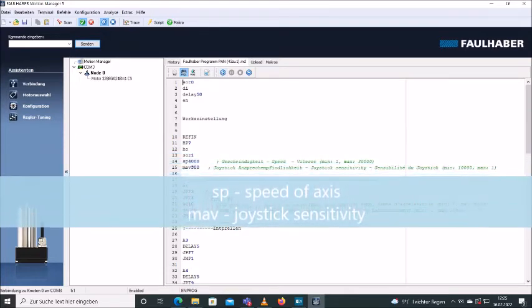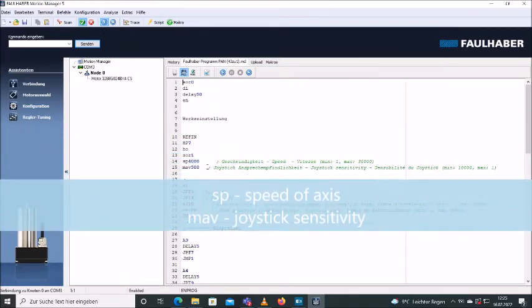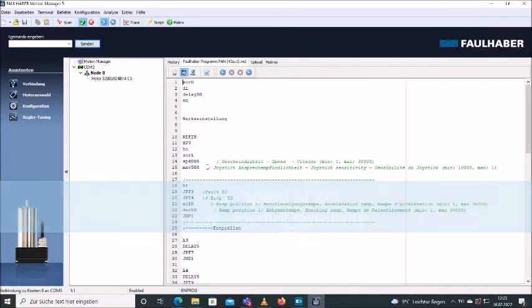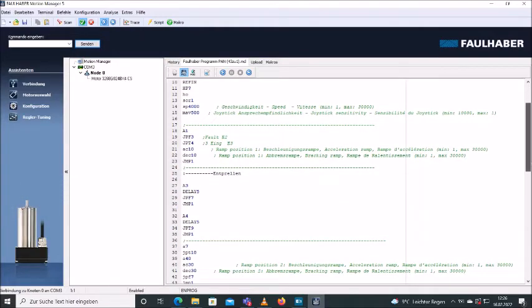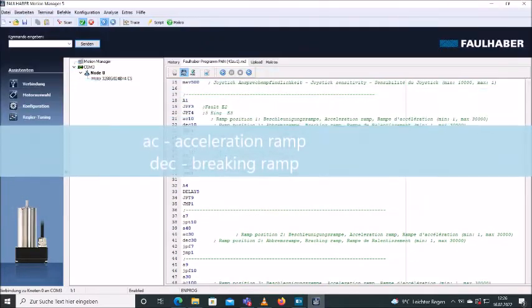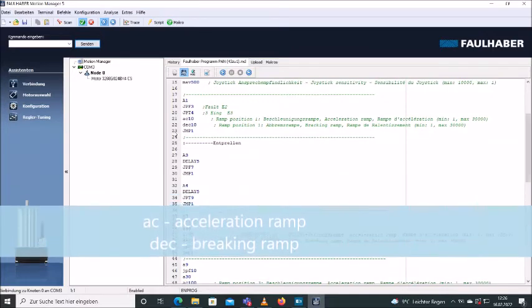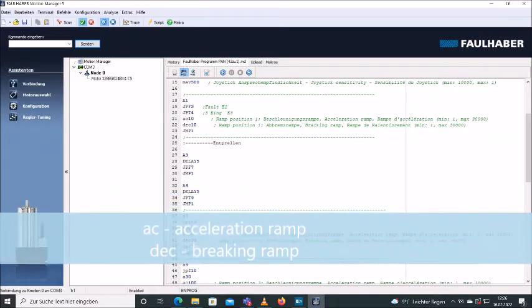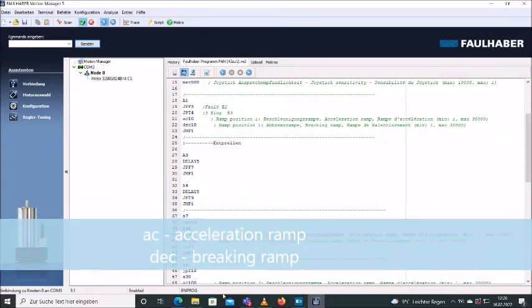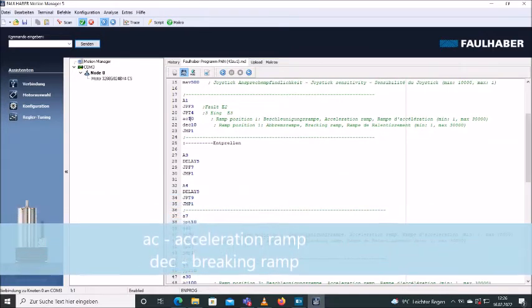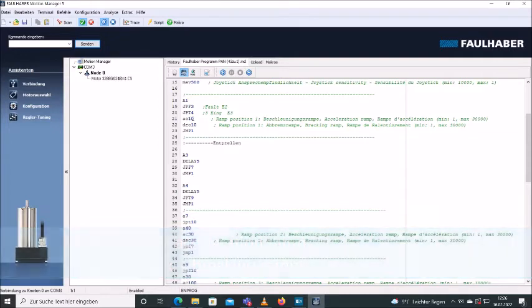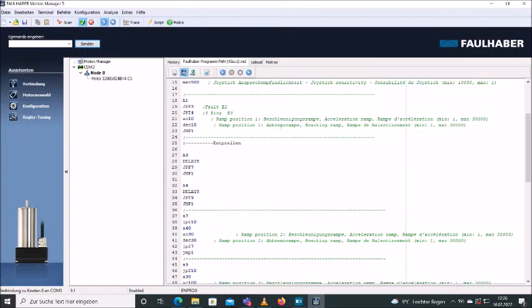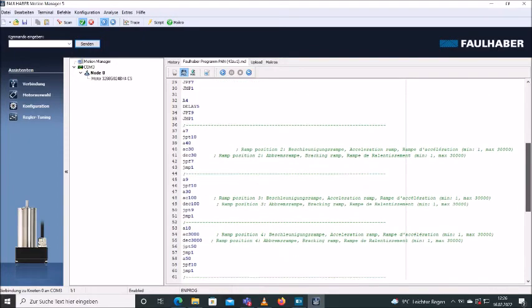MAV value—that's the sensitivity of the joystick. And we also have the ramp values, so for ramp position one, two, three, and four, which is the acceleration value, and the stop ramp, which can also be adjusted. You see the values are different depending on the position of the ramp switch.